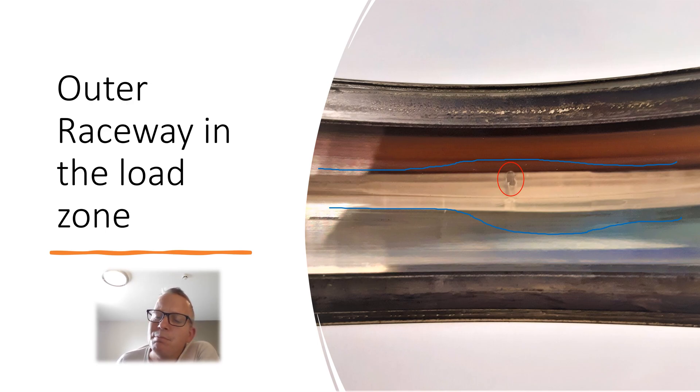So this dull bit here is common mode voltage from the variable speed drive. It's just a pattern often I've seen them. But this is going to be the load zone in the bearing which is going to get all the subsurface fatigue.